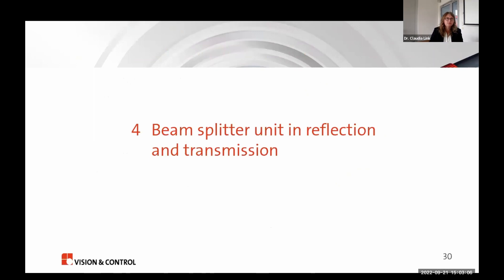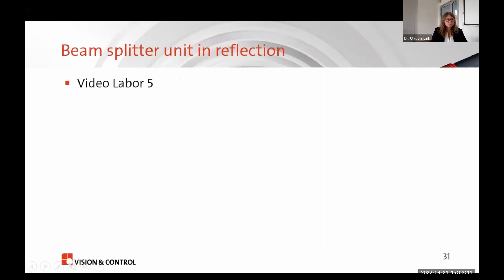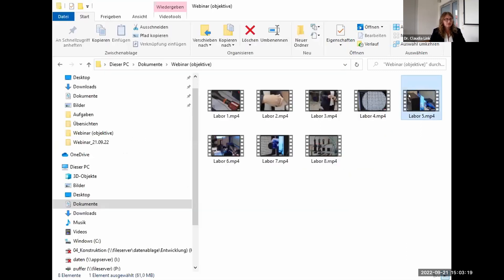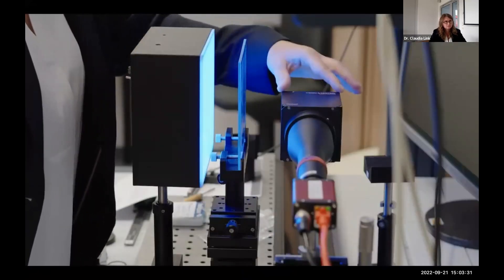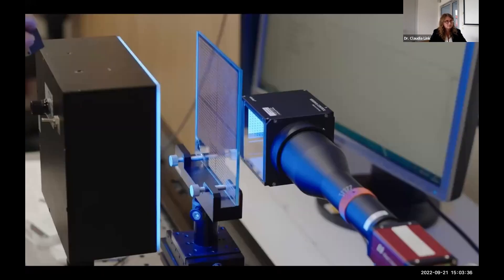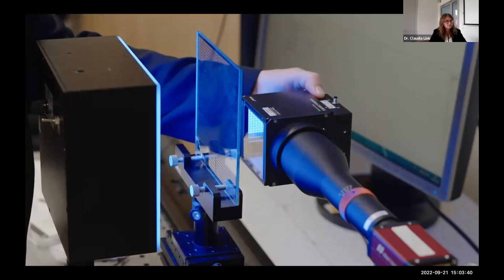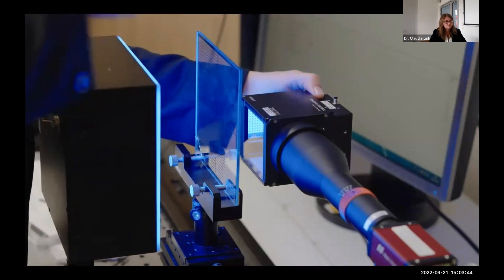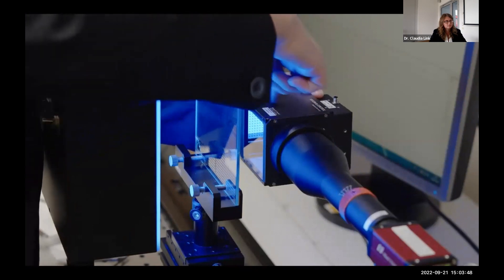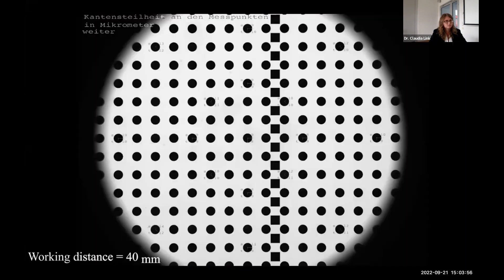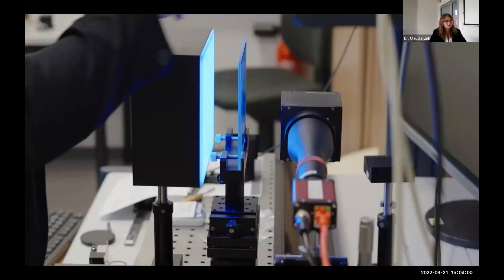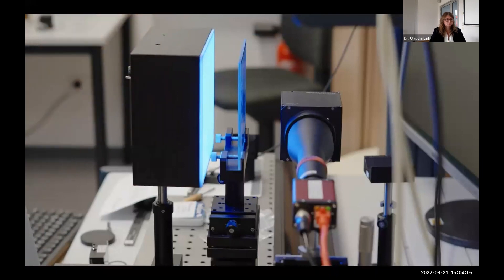Now I want to come to the beam splitter unit, used in reflection or transmission. The adapter fits the lens and allows imaging of objects in reflection with the help of a top illumination. When using the reflection path, you get a sharper image since the beam path does not pass through the inclined glass plate — in contrast to transmission, where it does.